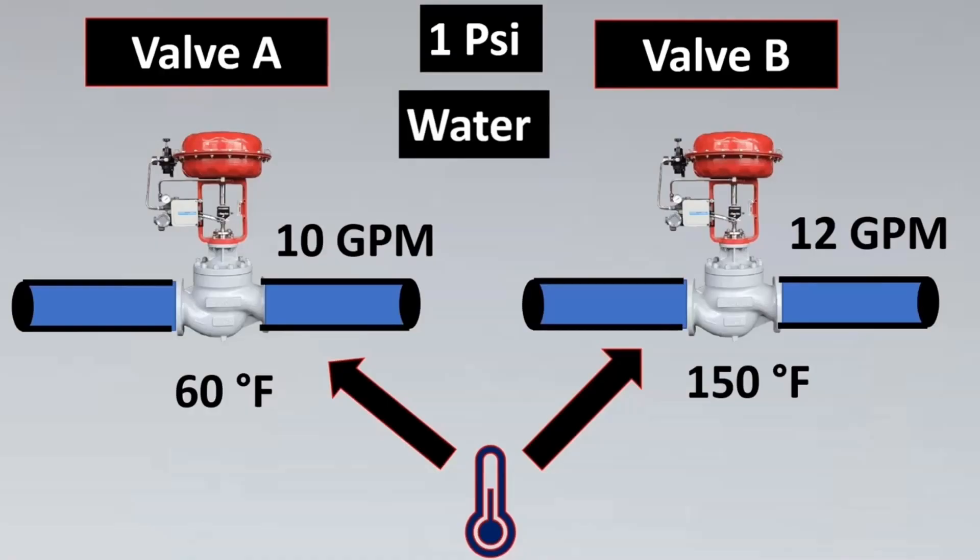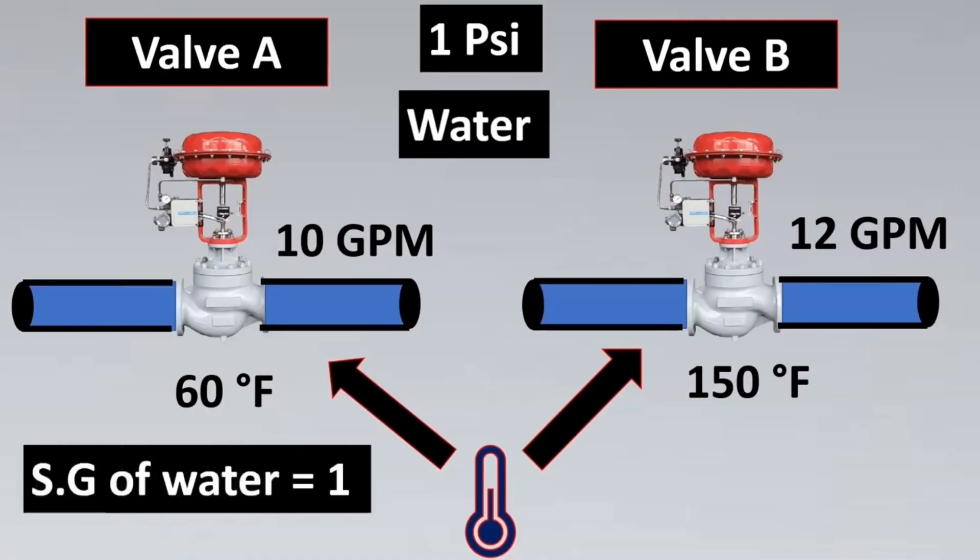A lot of people ask why 60 degrees Fahrenheit is especially taken in CV definition. The answer is because the specific gravity of water is 1 at 60 degrees Fahrenheit. This will help greatly when we are doing CV calculations.